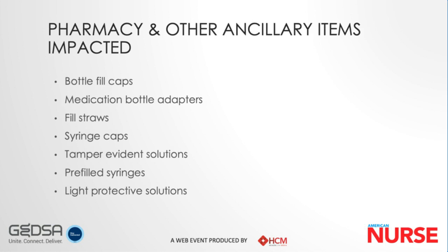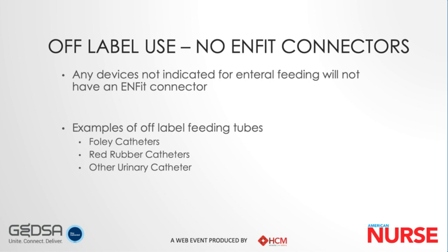However, if a device is used off-label, so things like a Foley catheter or a red rubber catheter, they are not going to be compliant with ENFit, and they're not required to be. The way I keep it straight is any device that's used to deliver something to the body, so enteral nutrition, enteral supplements, or pharmaceuticals, those types of devices that deliver something to the body will be compliant with ENFit. If a device, on the other hand, is used to remove something from the body, so for example, a decompression bag or a drainage bag, those will not be required to be compliant with the new standards.